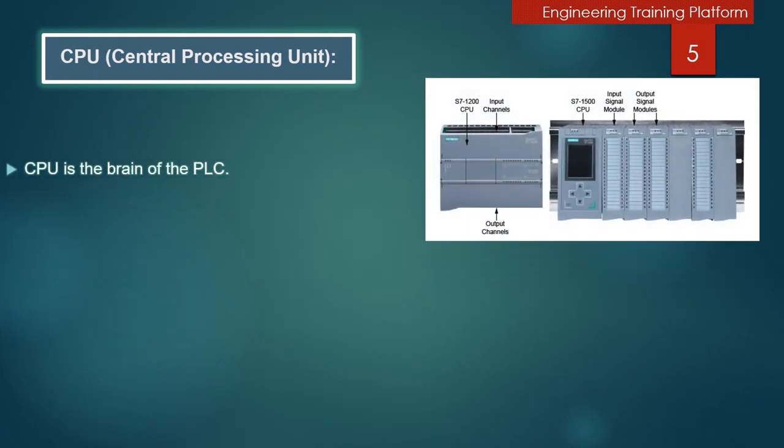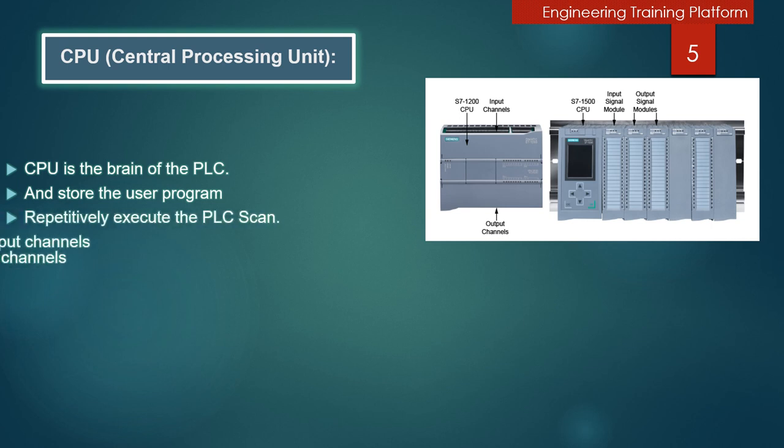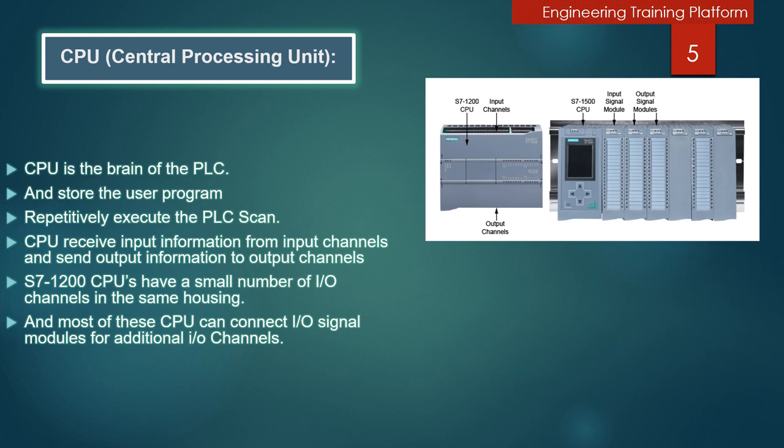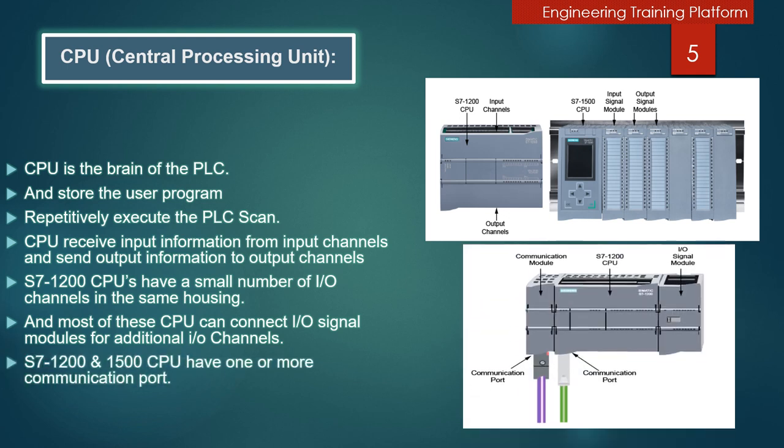I discussed about CPU in my previous lecture. But here is some detail. CPU is the brain of the PLC and stores the user program. It repetitively executes the PLC scan. CPU receives input information from input channels and sends output information to output channels. S7-1200 CPUs have a small number of I/O channels in the same housing, and most of these CPUs can connect I/O signal modules for additional I/O channels.